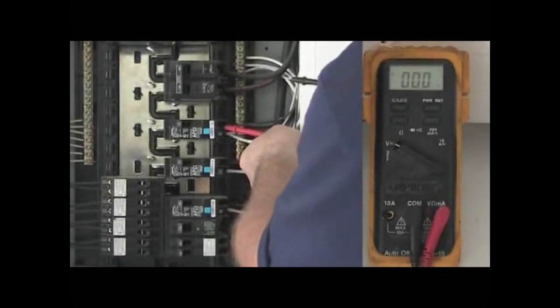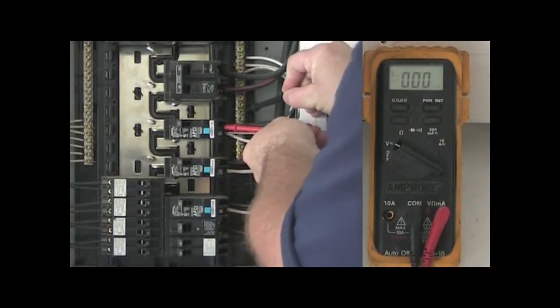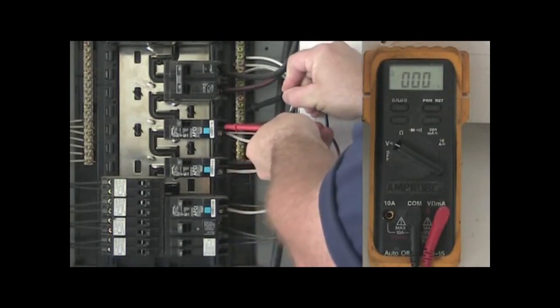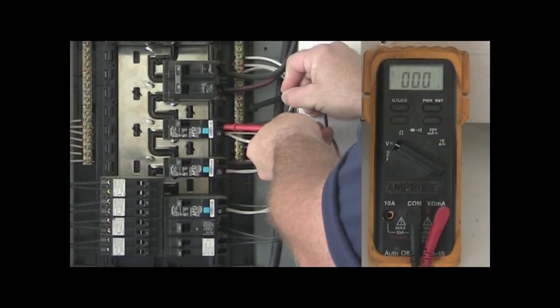If the breaker is bad, the voltage on this test will read anywhere from 0 to 109 volts. As a reference point, you should always take a voltage reading on the main breaker first. This will tell you if what you're seeing on the breaker being tested is normal.